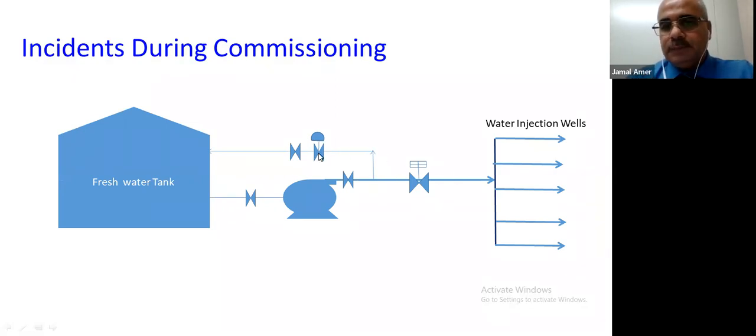As you know, when we want to start a centrifugal pump, we have to throttle the discharge valve to avoid pump tripping or motor tripping on overload if the discharge is open 100%. So we have this shutdown valve. It takes about one and a half to 2 minutes to be 100% open. During this time the pressure of this pump will increase. During startup, the recycle valve should open, returning the excessive surplus fluid to the tank.